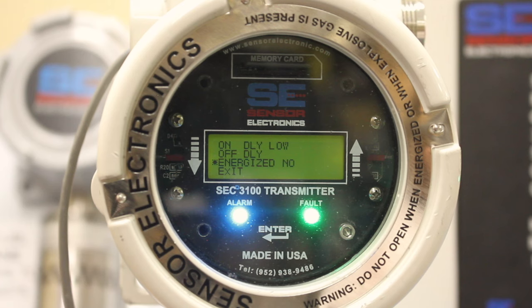We also have the capability of changing the polarity of the sensor, so we can change it to be normally energized or normally de-energized. So what this indicates now is energized no, so that means that the coil of the relay is not energized, but it does become energized once the alarm level is reached. So if we want to normally energize that relay coil, and then once the alarm level is reached, it'll drop that coil out, opening up the circuit on the normally closed, normally open relays inside the head, we can program it to be that.